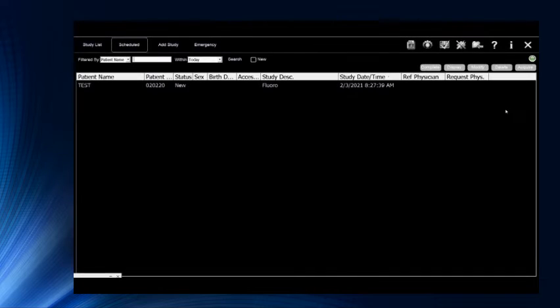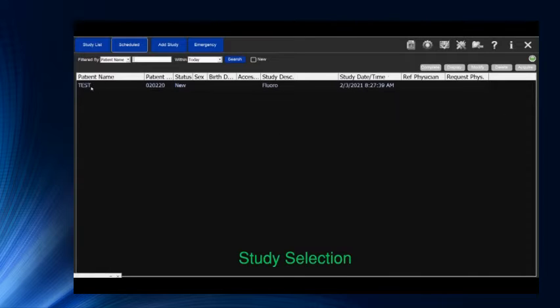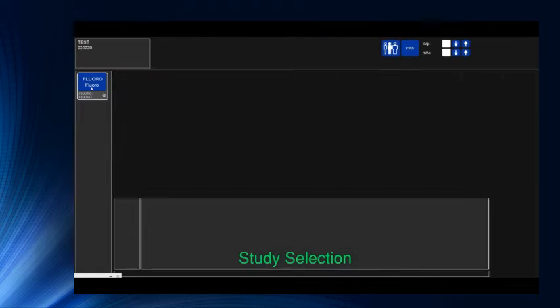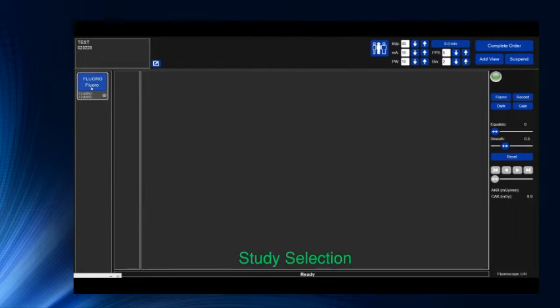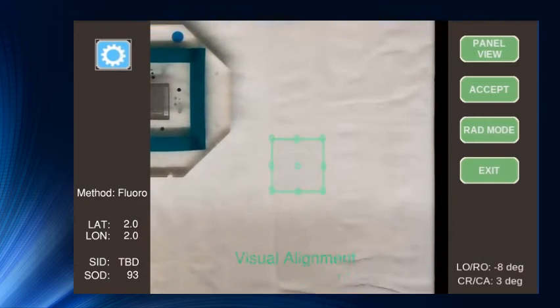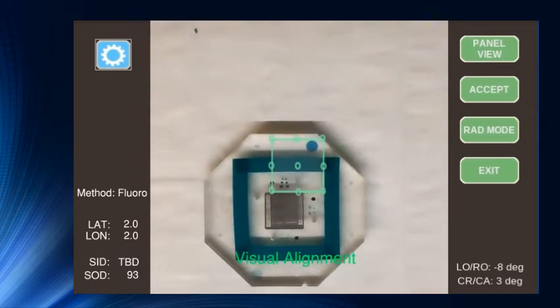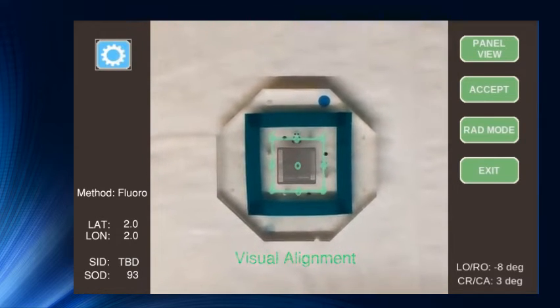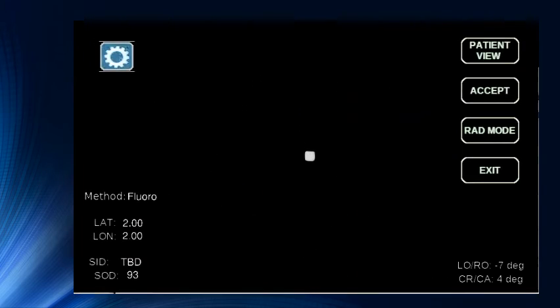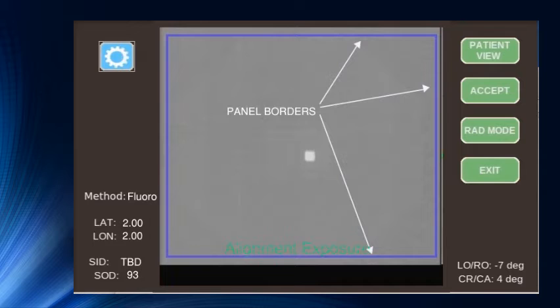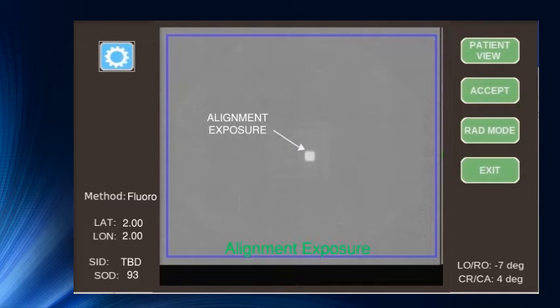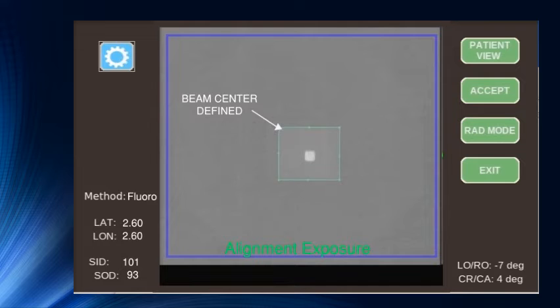For a typical procedure, the operator selects the fluoro option on the touch panel workstation monitor, then selects an APR station for the patient's size and anatomic region to be examined. Next, the operator places the detector under the patient and visually aligns the detector to the anatomic region desired. Then, the X-ray source is positioned over the patient, and visually aligned to the intended region by observing the live video image feed of the patient and the shaded virtual collimator area. The operator then initiates the alignment X-ray exposure, which is limited to a 1/2 by 3/4 inch radiation beam. The beam passes through the patient to strike the detector.